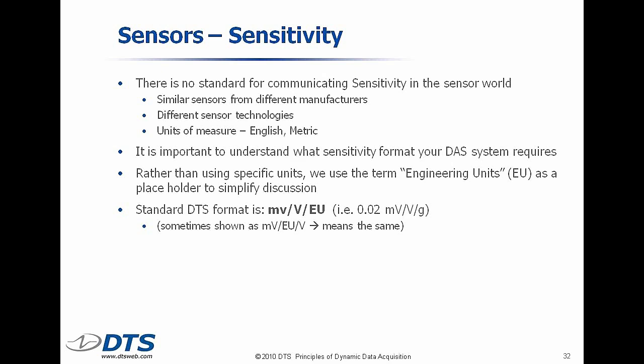Important to note, there truly is no standard for communicating transducer sensitivities in the world. Transducers of different types communicate it differently. Similar transducers from different manufacturers communicate it differently. It's important that you understand how to convert what the manufacturer for a sensor gives you into the numbers that the data acquisition system needs. Because they're not all the same. They all need that setup information.